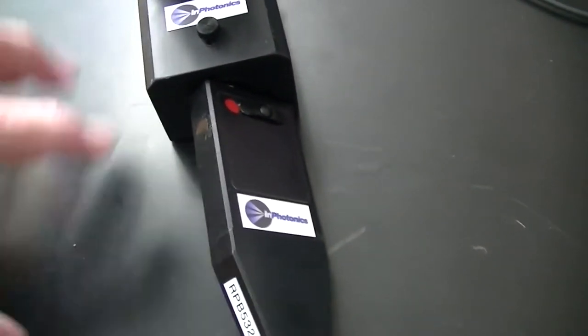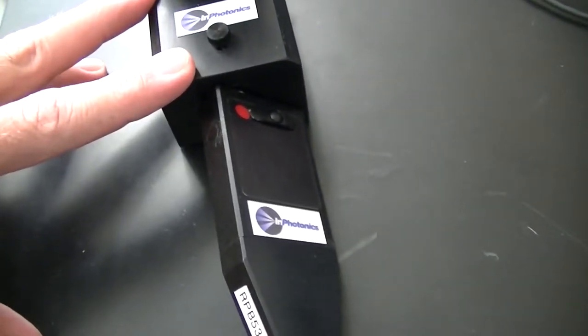There's a shutter on the probe here, and when it's turned to see the red dot, then the laser is able to exit the probe. So that's a safety feature. You can leave the shutter open while using the sample container, but at the end of the day, you need to turn it off like that.